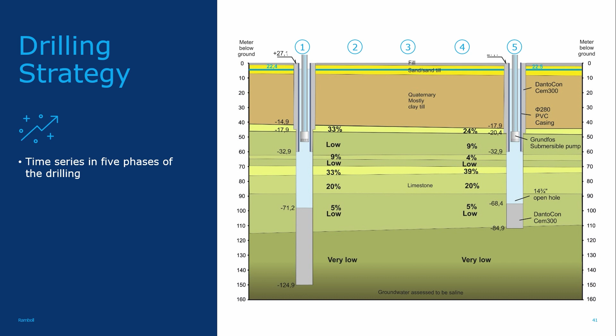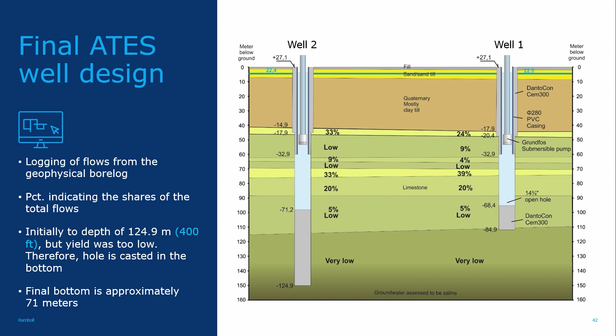For the final ATES well design, they were considering the different flows. Initially, it went down to a depth of about 400 feet, but the yield was too low. So the final is at about 250 feet, roughly 71 meters - I didn't do the exact calc on that one.